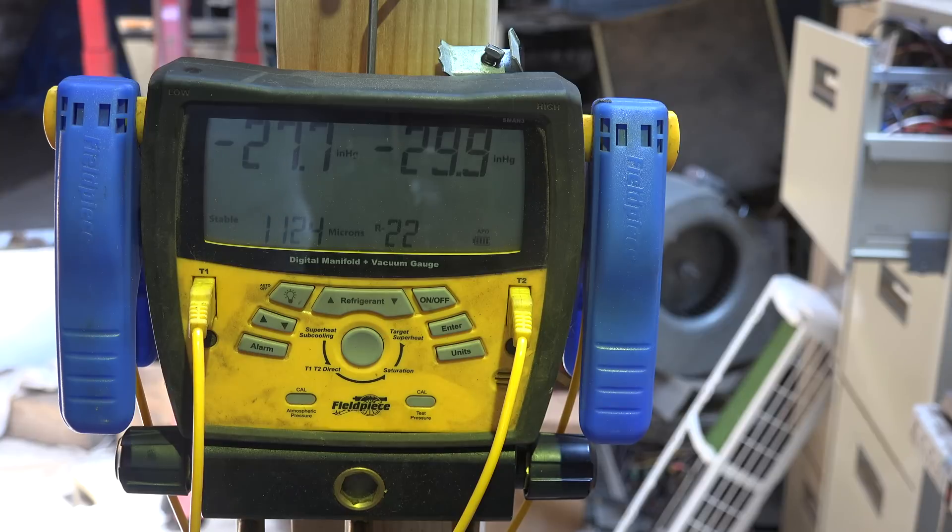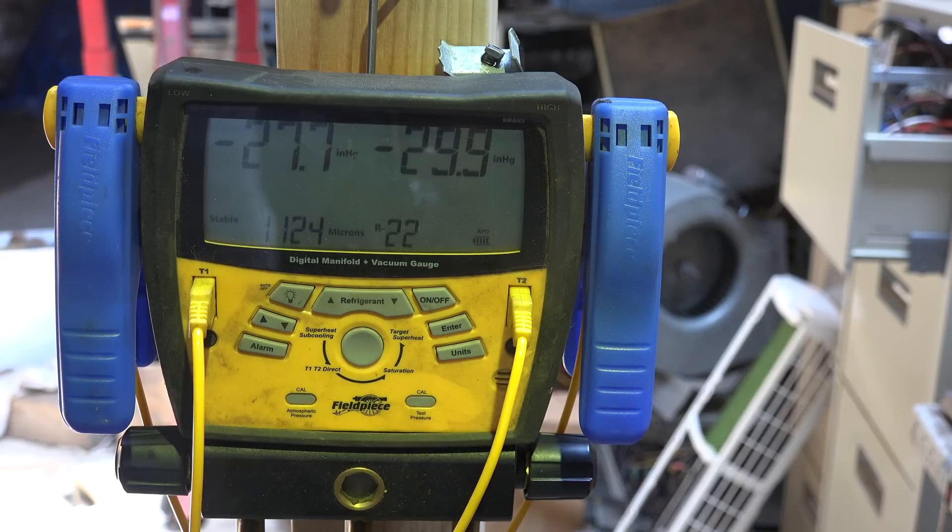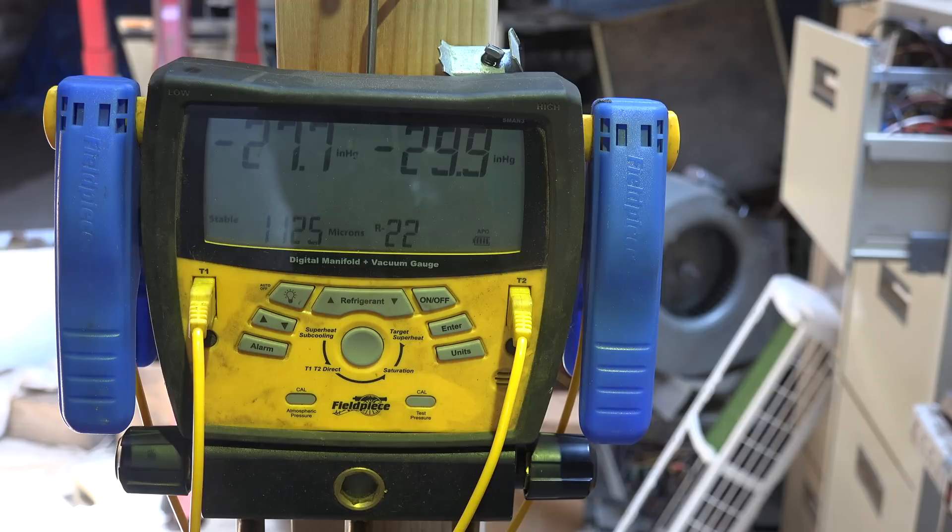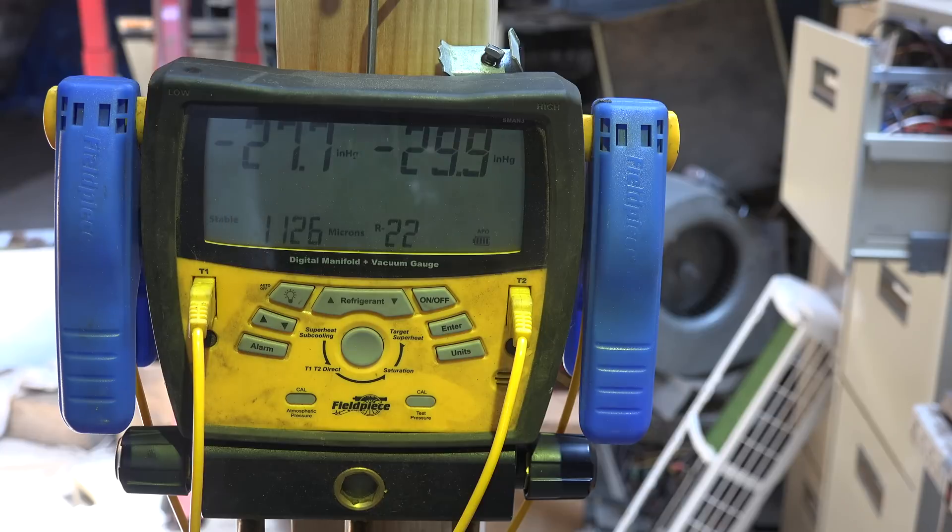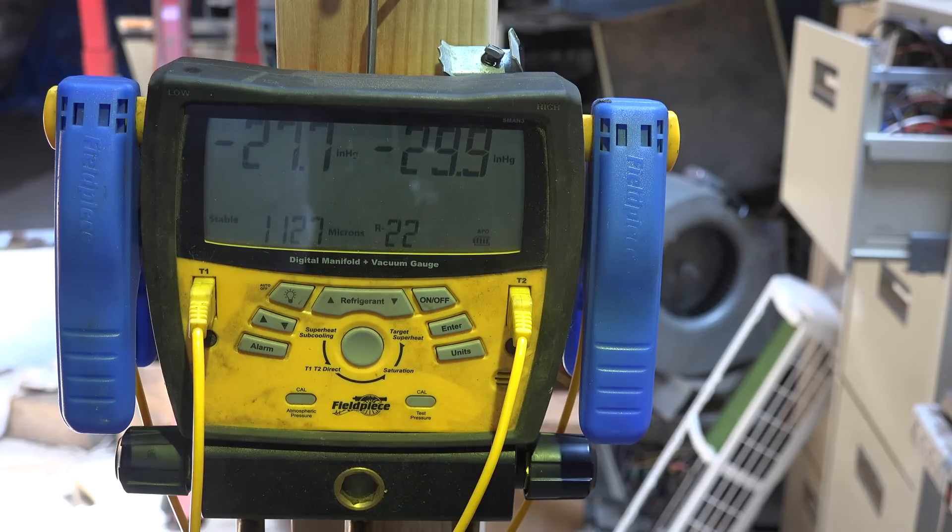What's happening is the moisture is boiling off because of the low pressure in the system. But once that pressure gets up to the boiling point of the water, it just kind of stops.